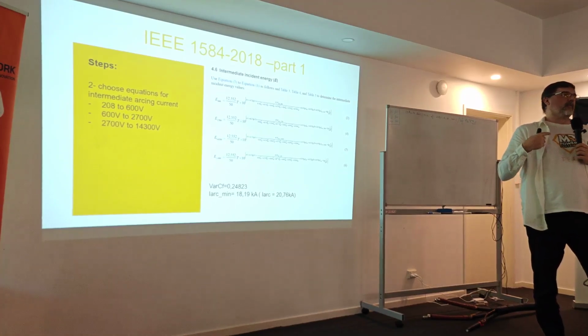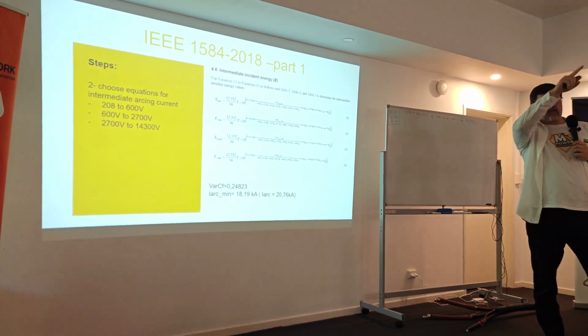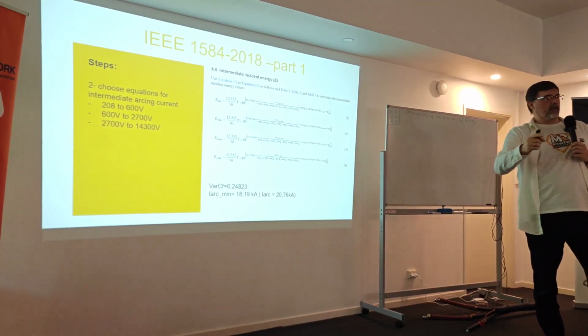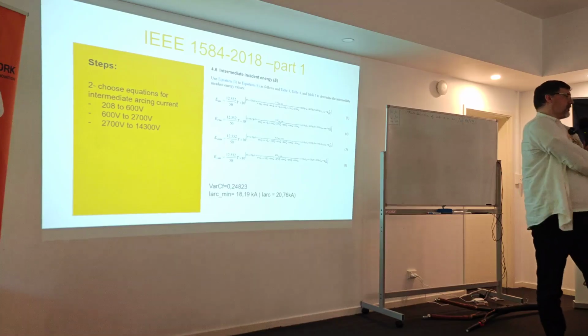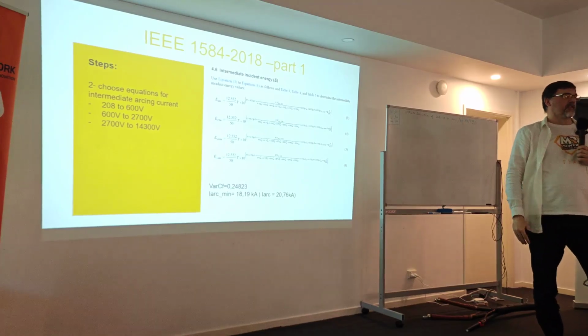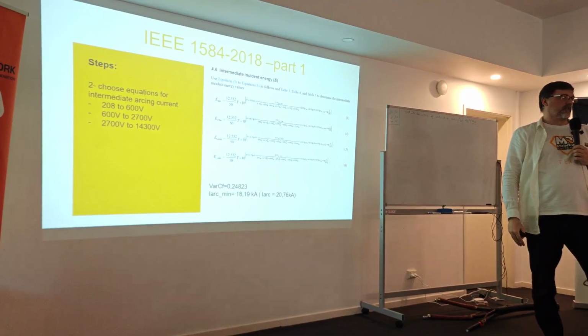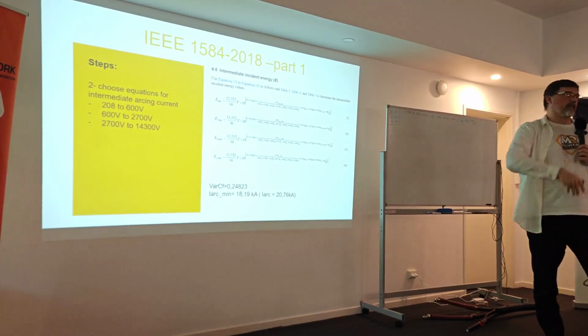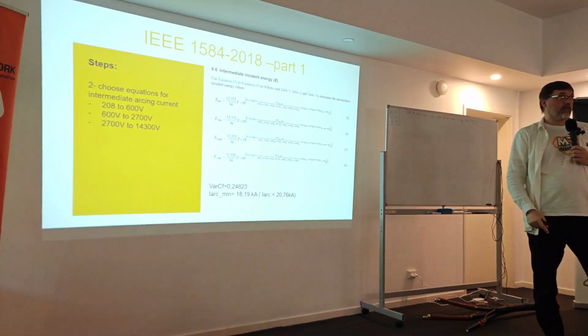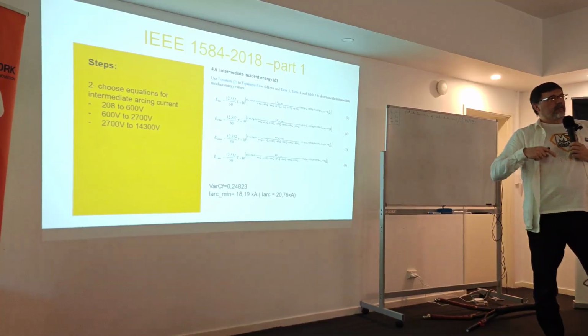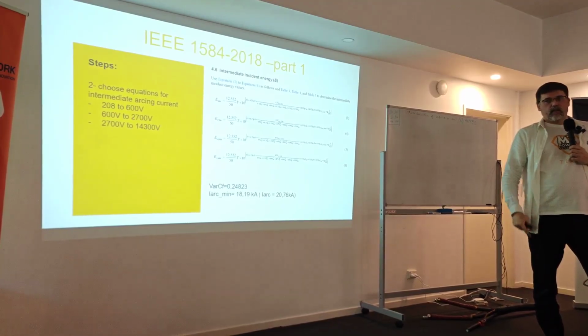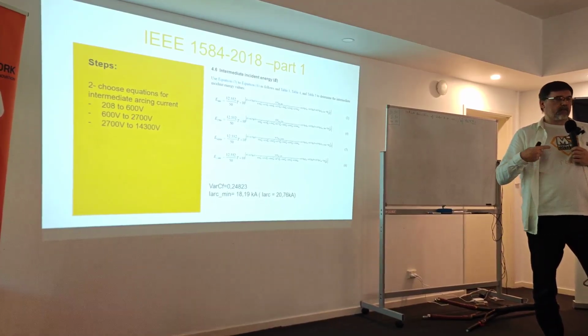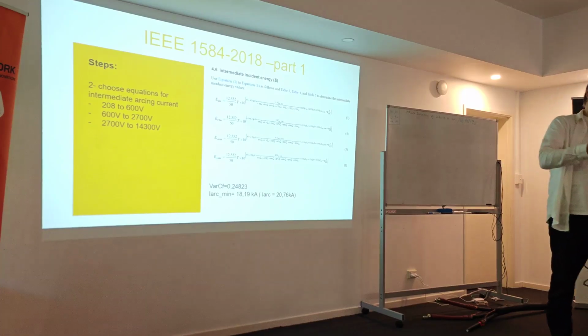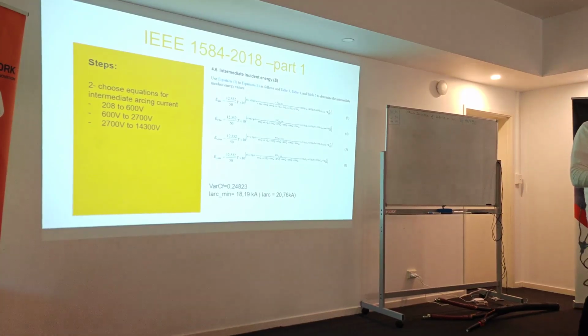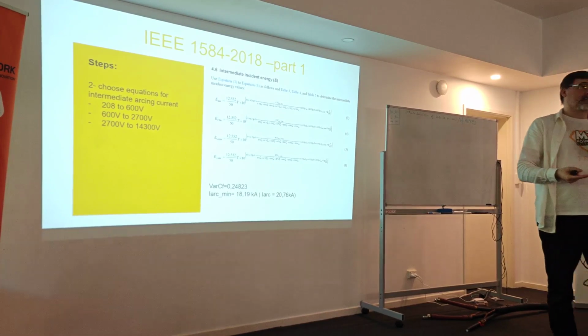And then someone will tell you, no, Marcin, but actually we changed this because it's not true, and you have to change this, and then you reconnect the cable, and every result is changed. So in Excel, this is probably something like 2 days of work, just to update something, and in the software it's just, okay, you reconnect it, you rerun everything, it's a few hours of work, maybe not more than 2 days. So in my feeling, Excel calculation and hand calculation are just discouraging people from doing any updates, because they know that when they do it, it's a lot of work.